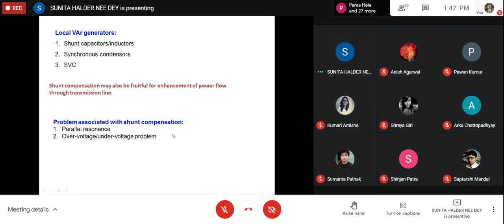Over voltage and under voltage problems may happen if you connect the wrong compensation. During Ferranti effect, if you connect a capacitor again, there will be an over voltage problem. During heavy loading condition, if you have connected an inductor, there will be an under voltage problem. So these things are to be taken care of.